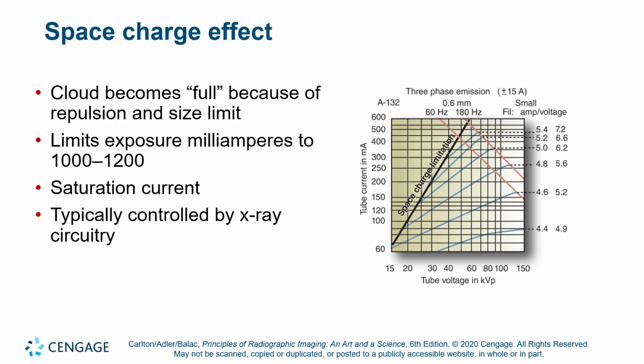And so what that means is there's only so much thermionic emission you can generate. You get maximum cloud volume. We call that the saturation current, and it's about 5 amps of filament current. Okay, at about 5 amps of filament current, you get this threshold where you can't stuff any more electrons into the cloud. Okay, if you run lower filament currents, the capacity of the cloud is even less. Okay, and you can kind of see that on this chart.